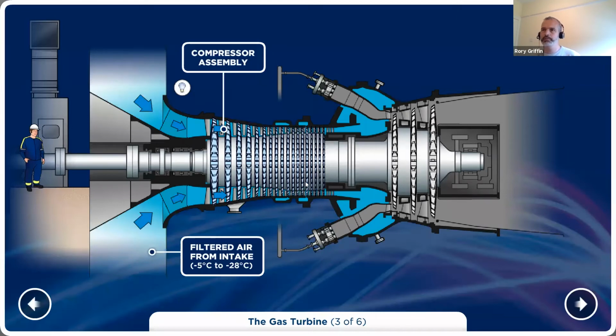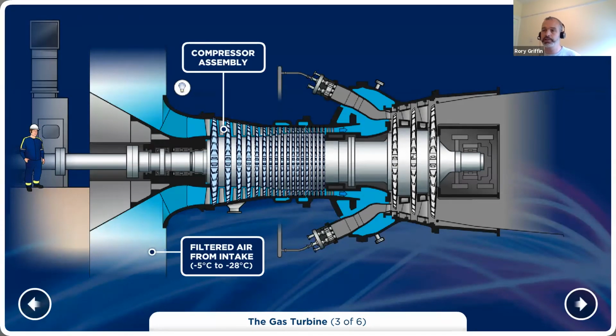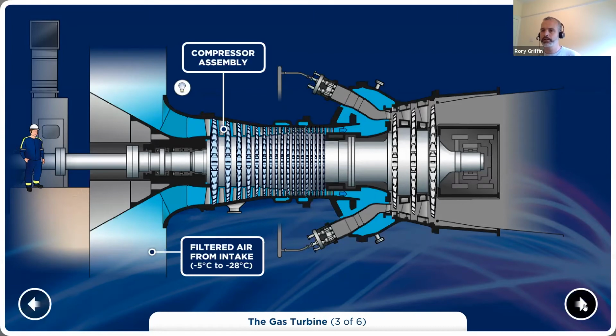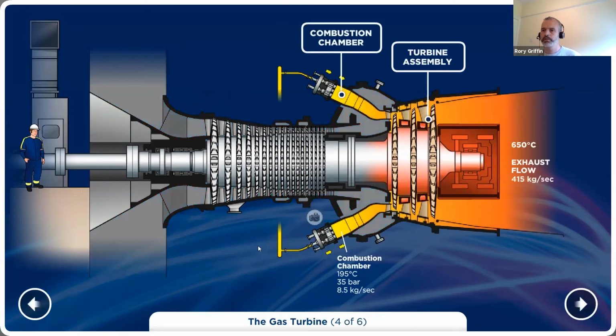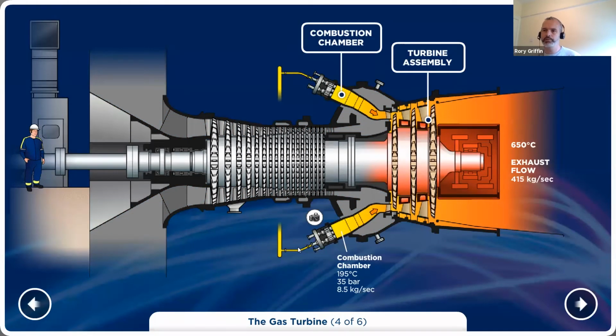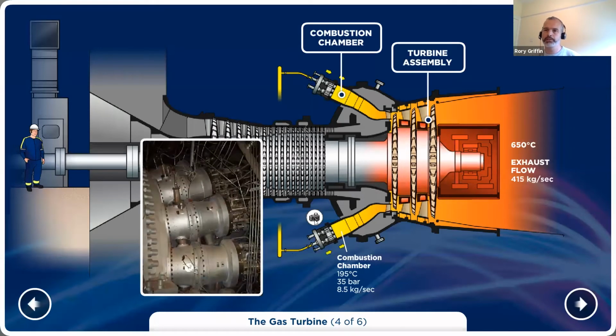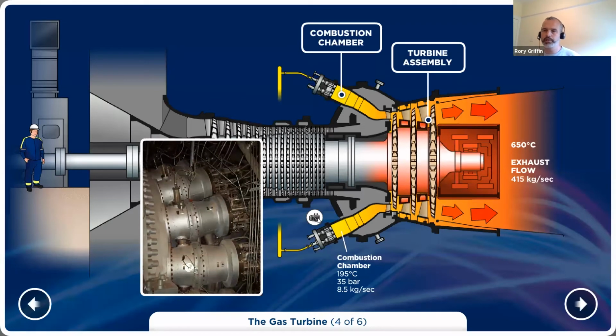Next, we get to the power turbine. So this is what we'd refer to as the 3 stages of blades here. So this is the gas turbine itself. And I'll just bring in the gas fuel. So the flow rate here is about 50 tons to 55 tons, depending, I suppose, on the loading on the machine. This is what the combustion can looks like. Quite a lot of pipe work on it. I suppose bear in mind it's a dual fuel unit.